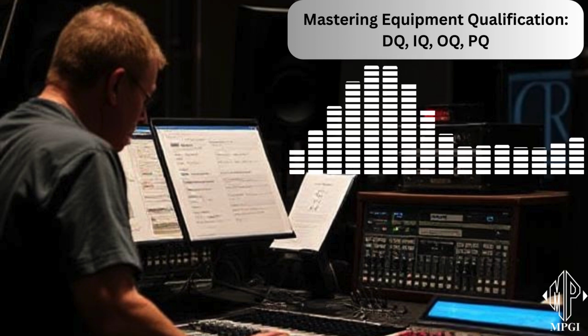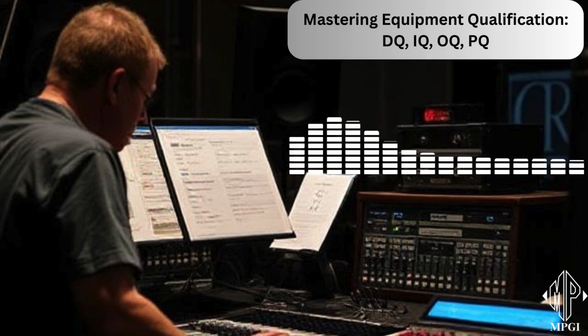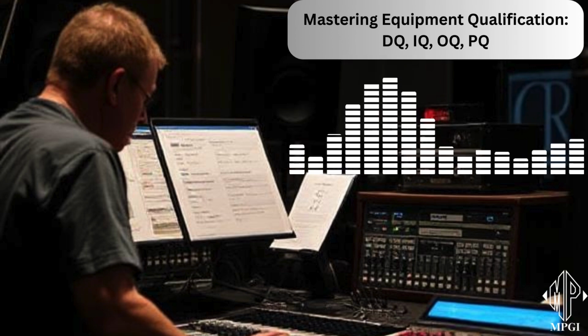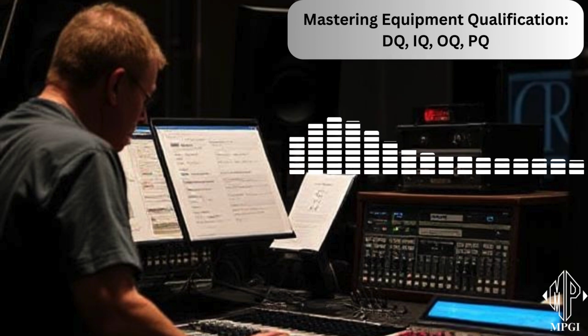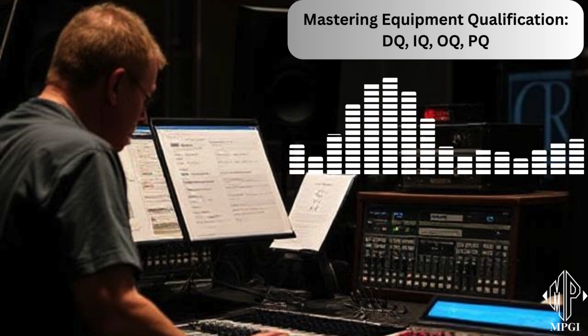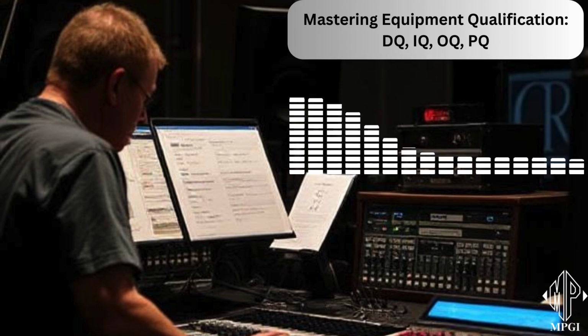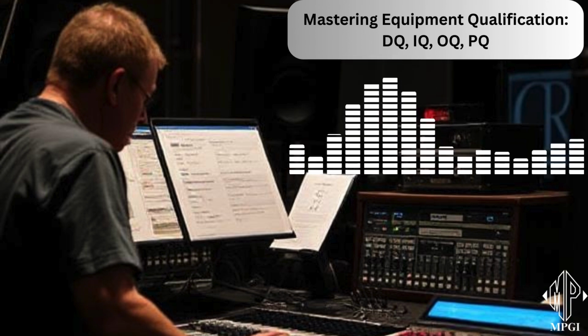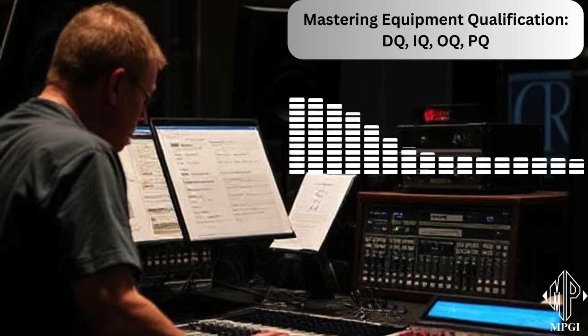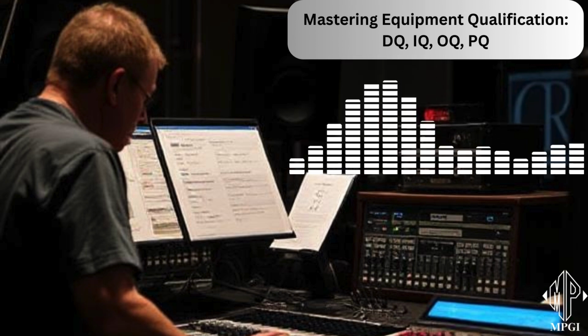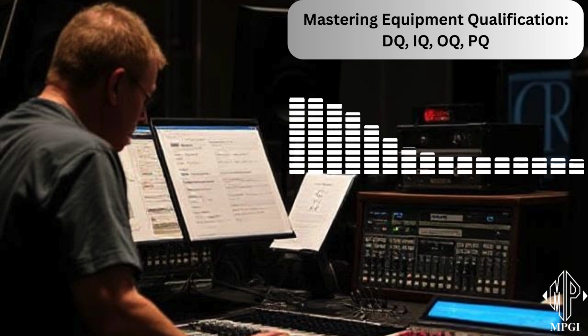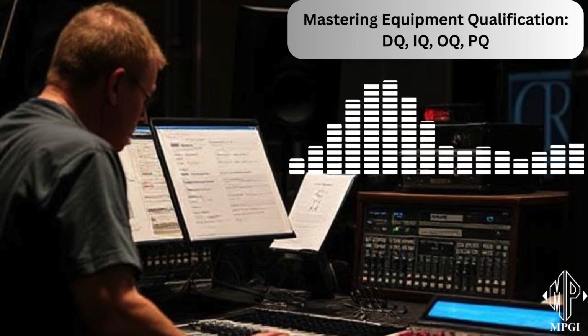Okay, can you give us some real-world examples of OQ tests for different types of equipment? Sure. Imagine an autoclave, which is used for sterilization. Essential for keeping things germ-free in a pharmaceutical setting. Exactly. They might do temperature mapping with an empty chamber and a simulated load to ensure even heating throughout the sterilization cycle. So making sure the temperature is consistent everywhere inside the autoclave. Right. They'd also test the alarm systems, making sure they go off when they're supposed to. And of course, they'd check the overall sterilization effectiveness. Making sure it actually kills those germs.